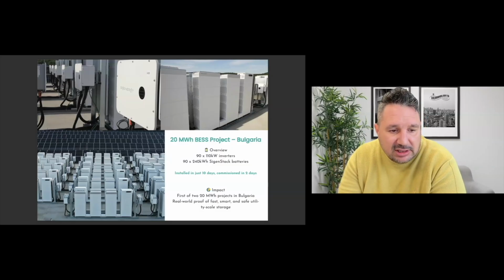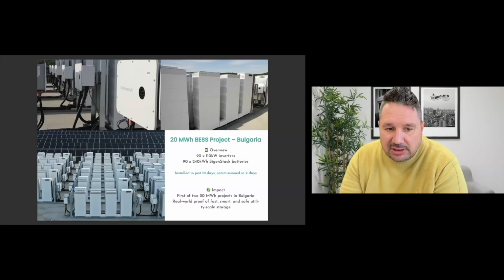So when you commission the site, you literally open the app, you scan the barcode, and it runs a full diagnostic check. If you have somewhere down the line maybe swapped around a positive and a negative on your PV connection, or you've got a battery connection that is not properly done, the system will first run a full diagnostic check, and when it has picked up that there's a fault, it will reply to you on the assistant saying that if you check inverter number 7, the battery connection is not done properly. If you check on inverter number 9, MPPT number 1, the PV positive and negative has been swapped around. So the system won't switch on if there's any fault on the system. It will first run a full diagnostic check and then only allow you to commission.